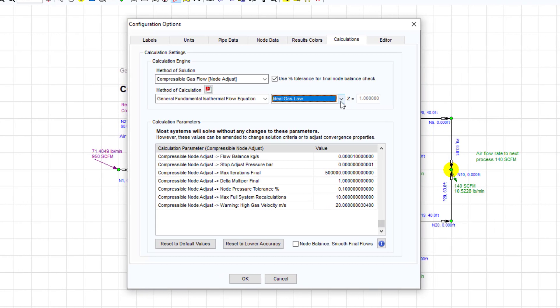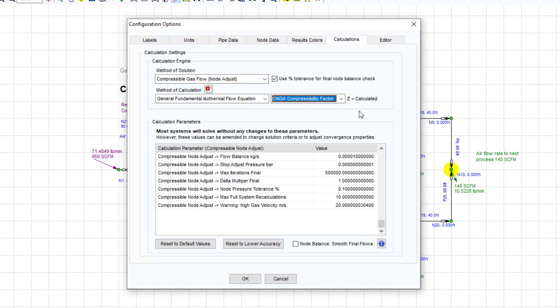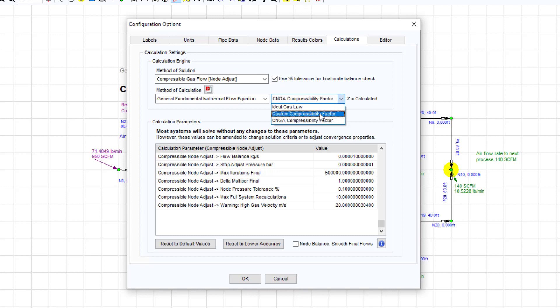Real gases behave according to the ideal gas law modified using a specified gas compressibility factor Z. The calculations can incorporate the ideal gas law, the CNGA compressibility factor which is calculated from each pipe based on the pressure at the start and end of each pipe, or a custom compressibility factor which is applied to the whole network.